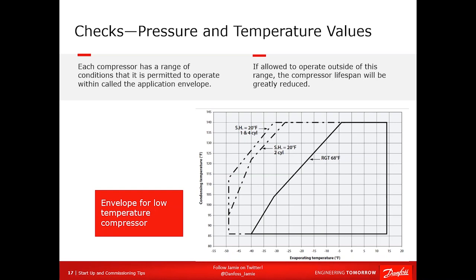Now, one of the important things here is superheat. So you'll see a range of temperatures at the bottom and a range of temperatures on the left-hand vertical column. You'll notice this is a low temperature compressor. So it operates just below 15 degrees Fahrenheit down to minus 50 almost. As long as your superheat is low, it'll operate down to minus 25, maybe even minus 30 for certain models, and still have adequate cooling.